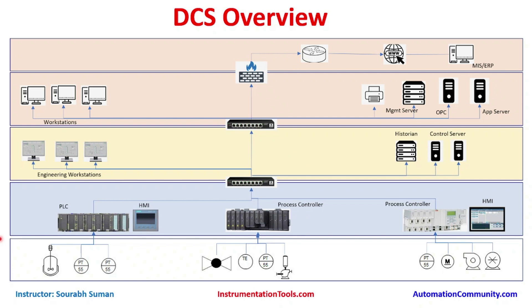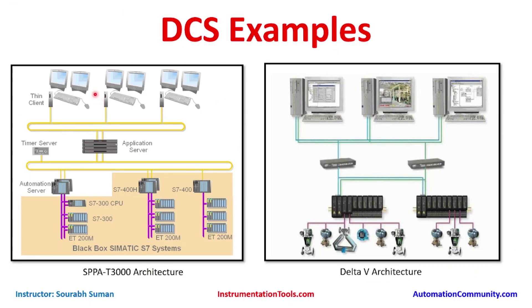Now let's look at some DCS solution examples. Here we can see a sample architecture of SPPA-T3000, which is a DCS solution by Siemens. In the field, it starts from the IO cards — the ET200 modules — which are connected to the S7-300 CPU, or it could be an S7-400 or S7-410. All automation-related things are then connected to the automation server.